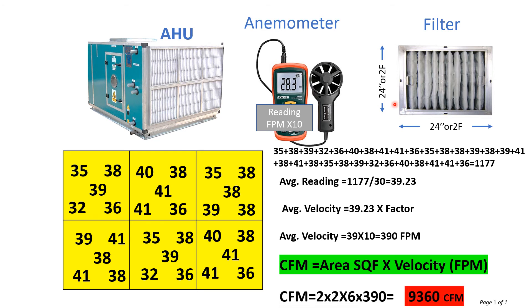So: 2 × 2 × 6 filters, with the average velocity of 390 FPM — the total CFM is 9,360.